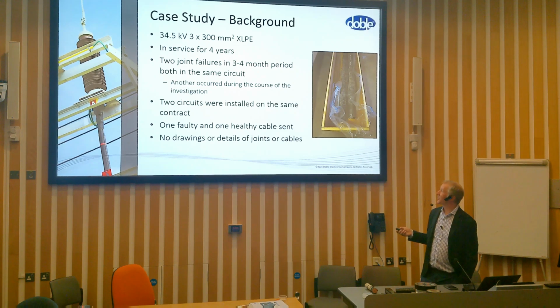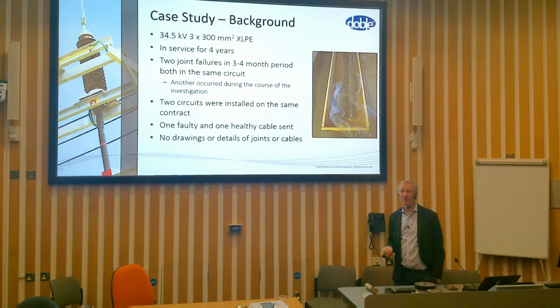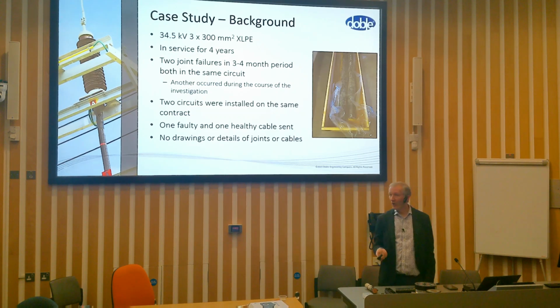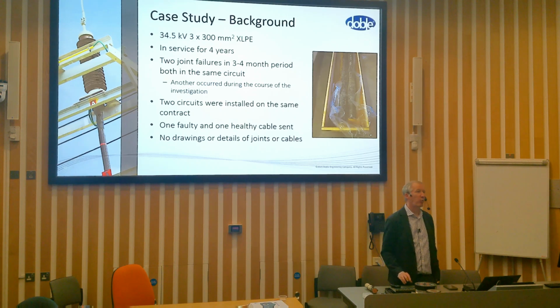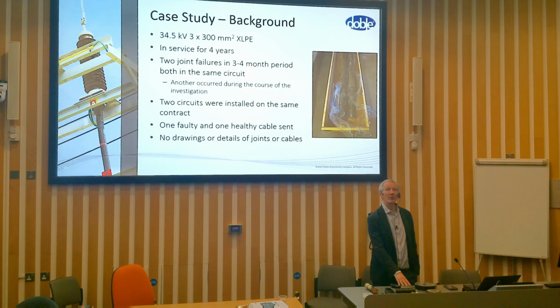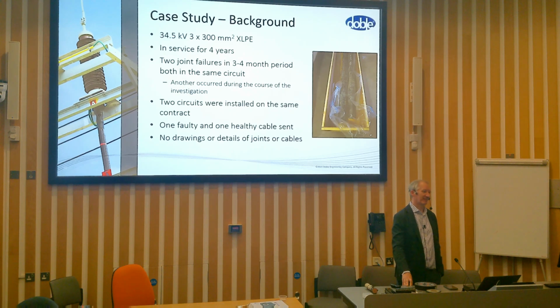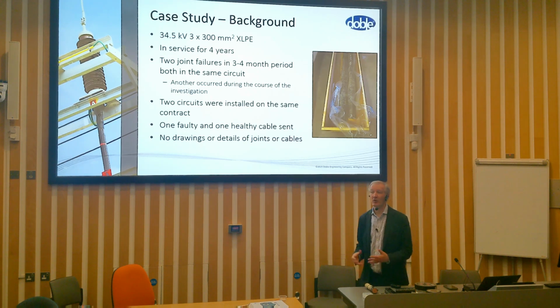Sometimes, and this happens more with industrial clients than utility clients, they don't ever seem to have any paperwork. This had only been installed 4 years before, but they had no information on what the cable was, what the design was supposed to be, or what the joints were. So the first problem is you don't even know what you're looking at.